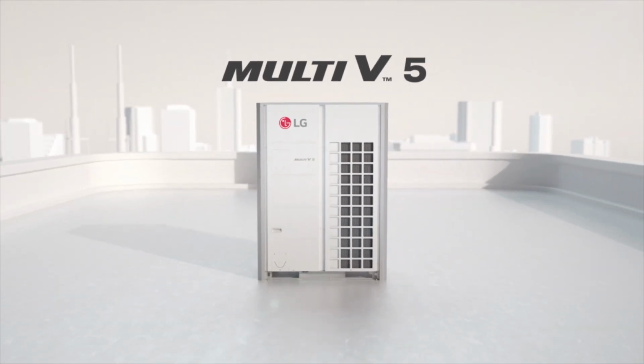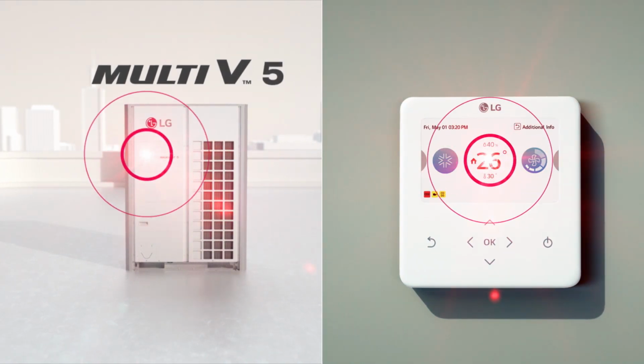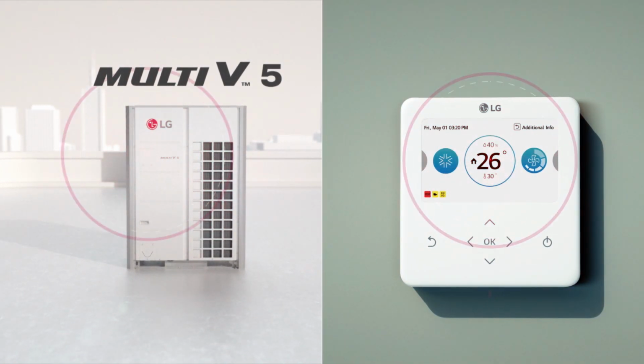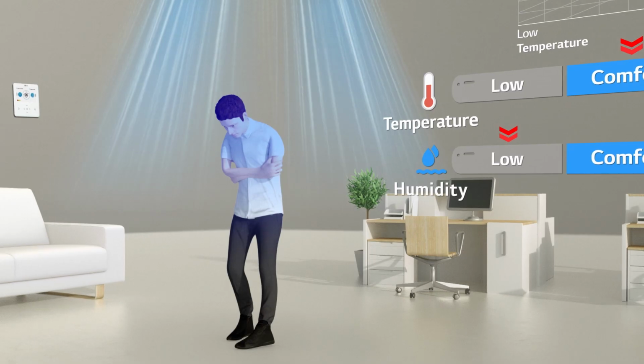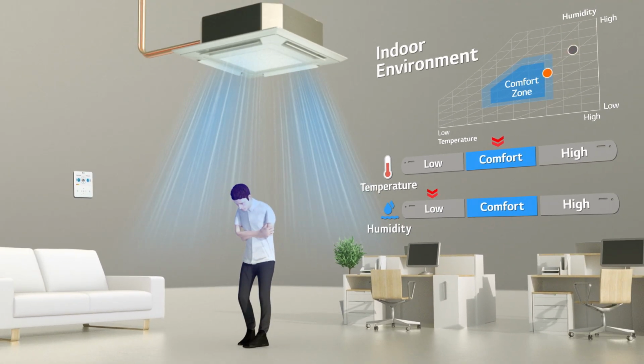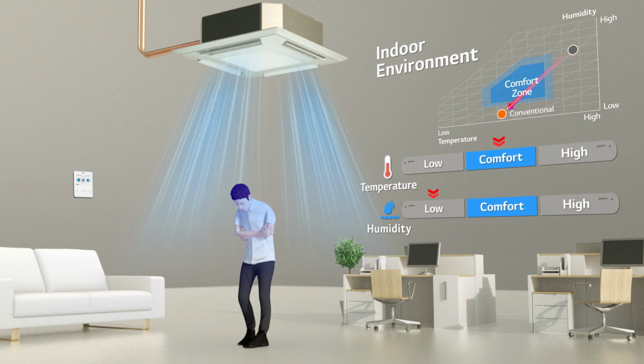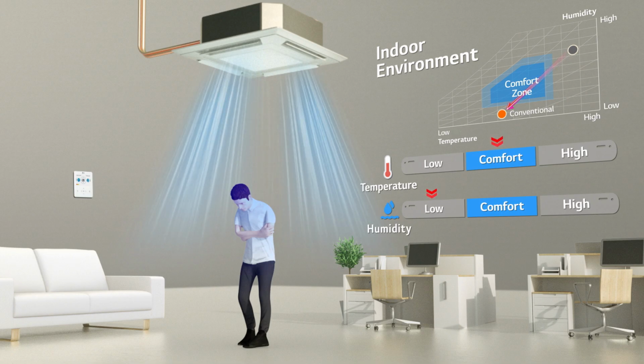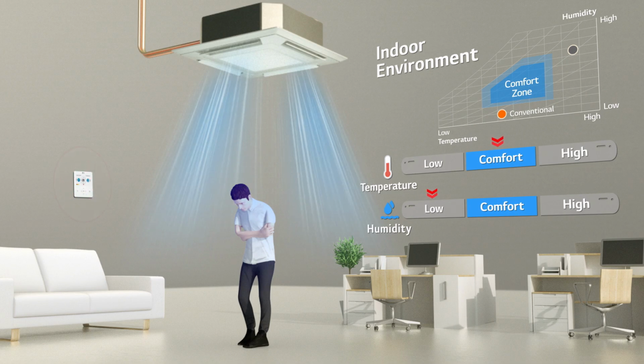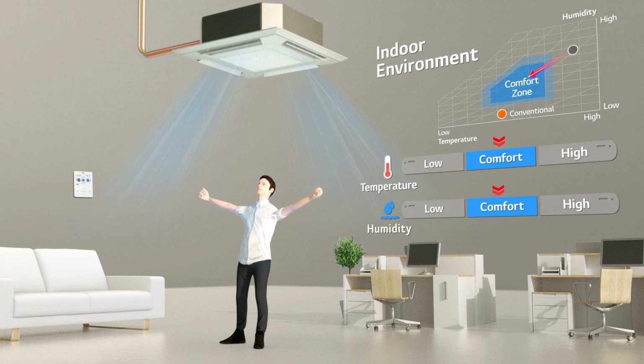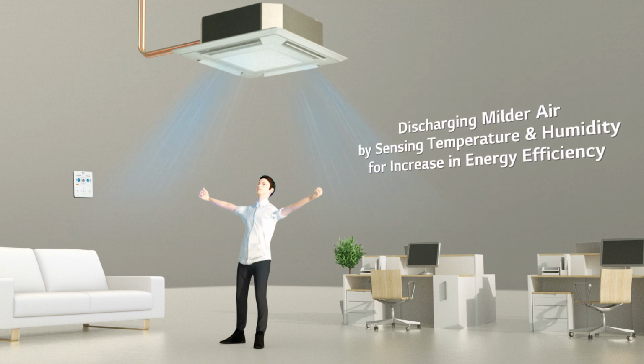This is why Multi-V5 was introduced, the VRF with humidity sensor that controls by sensing both the temperature and the humidity of the environment. Now you understand why this guy over here felt uncomfortable. After being overcooled, the place got too dry with low humidity. As Multi-V5 senses humidity level of the place, the discharged air is smartly adjusted, which eventually brings back the pleasant environment for the users. In addition, through the discharge of milder air by sensing temperature and humidity, energy efficiency is increased.